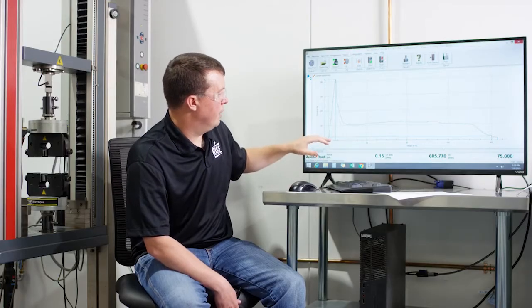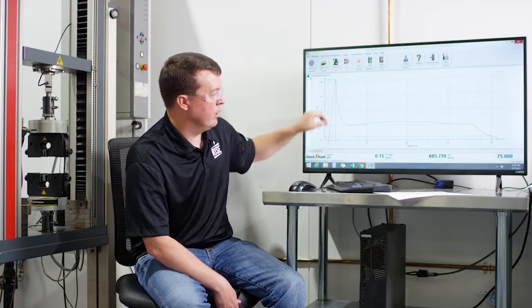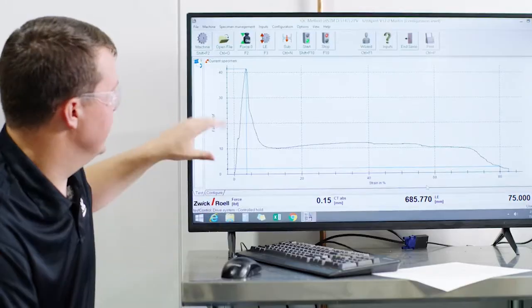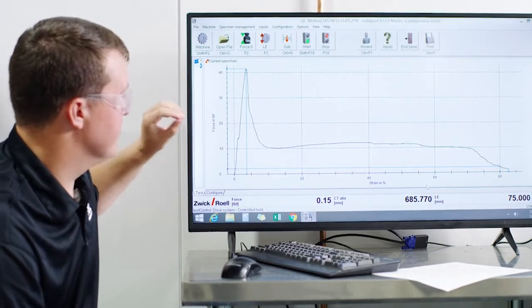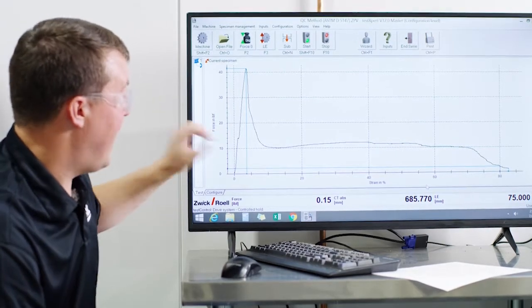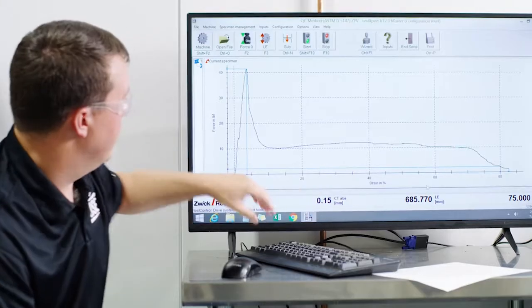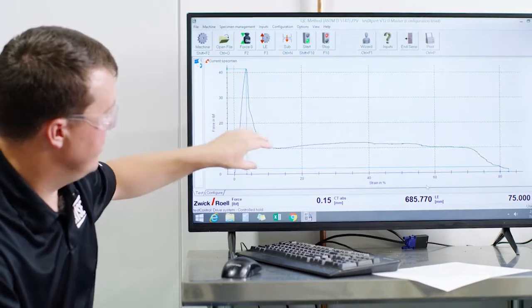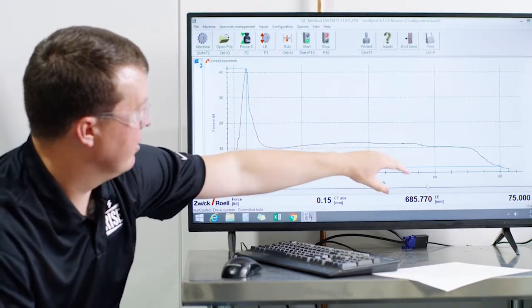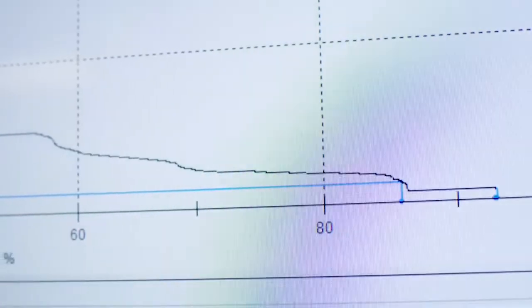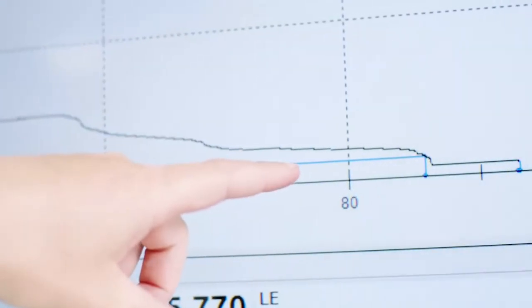Another critical point outside of peak load is the ultimate elongation. Ultimate elongation is measured after you reach 5% of the peak load. So here we've had the load decreasing down, and that measurement is not taken until we drop below 5% of this peak load itself.